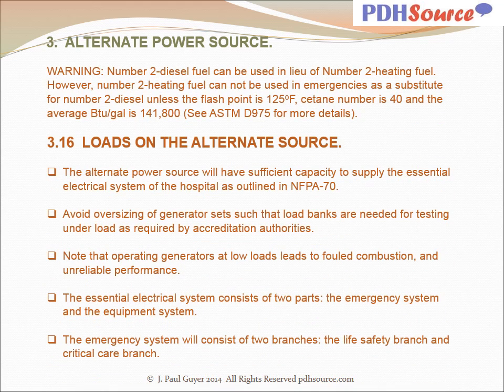Warning: number 2 diesel fuel can be used in lieu of number 2 heating fuel. However, number 2 heating fuel cannot be used in emergencies as a substitute for number 2 diesel unless the flash point is 125 degrees Fahrenheit, cetane number is 40, and the average BTUs per gallon is 141,800. Refer to ASTM D 975 for additional details.